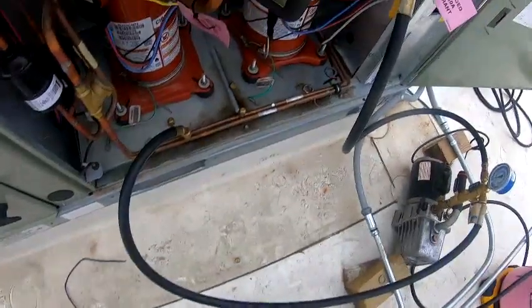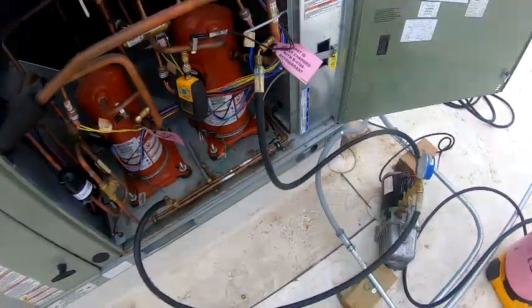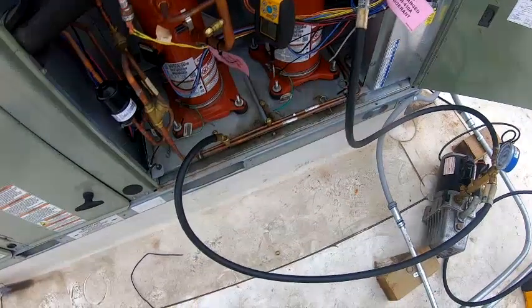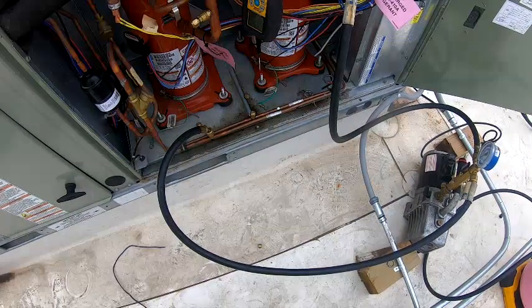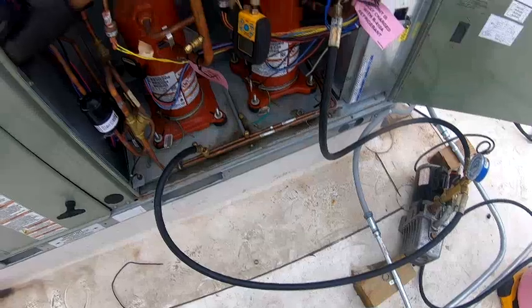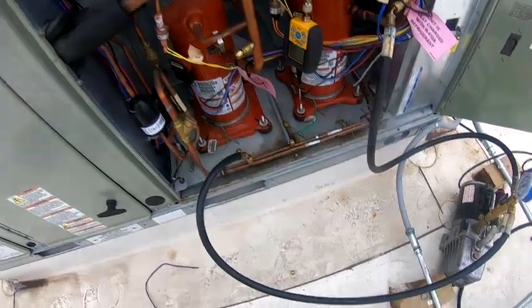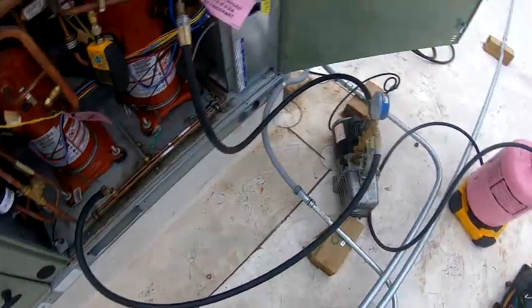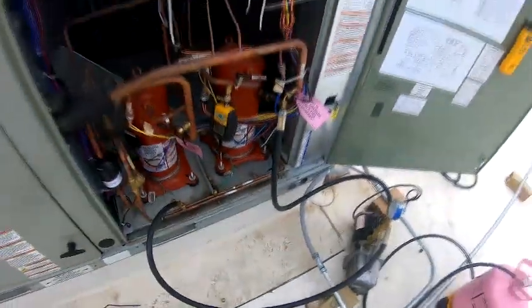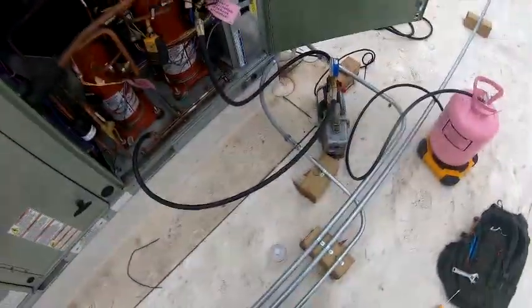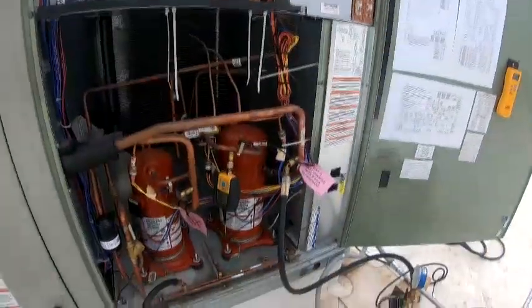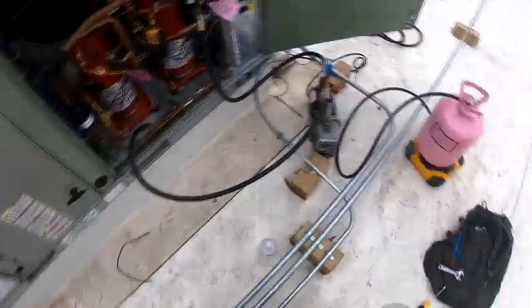So right now I'm still under 700 microns. I think it's probably been about 3 or 4 minutes. That's guaranteeing me I don't have any leaks or moisture in the system. So you can feel good, go to sleep at night knowing your refrigerant is not going to leak out. That's why it's very important to use a micron gauge and not play the guessing game.